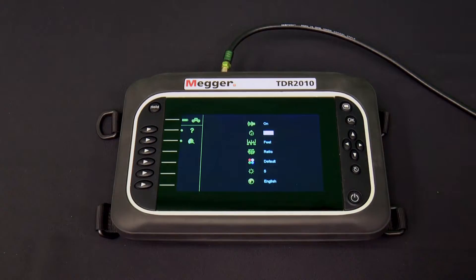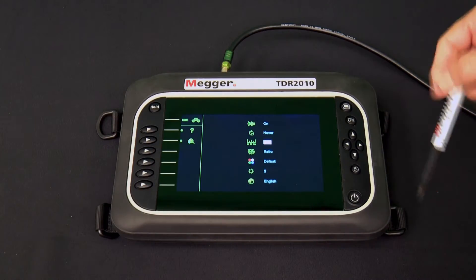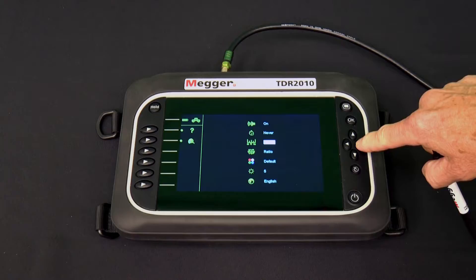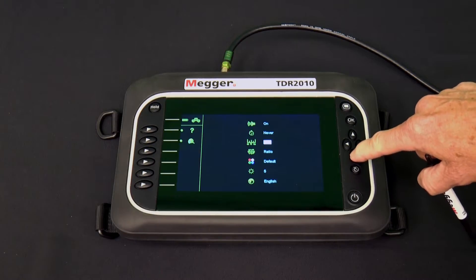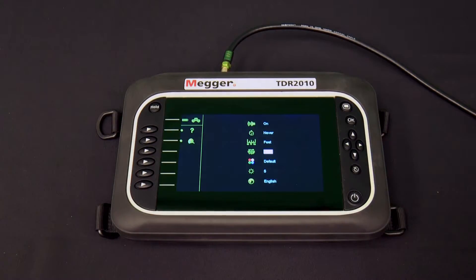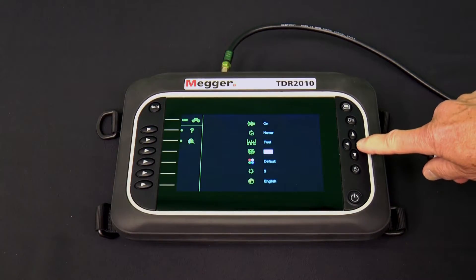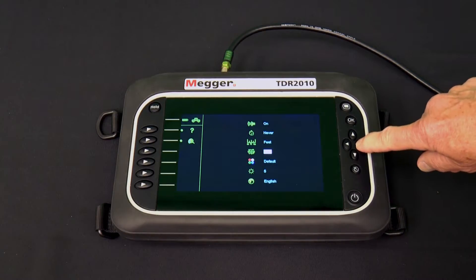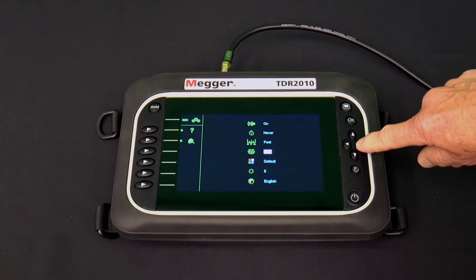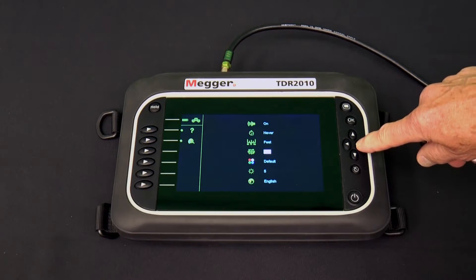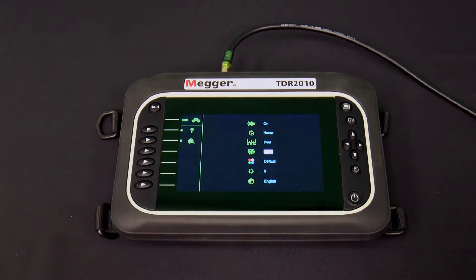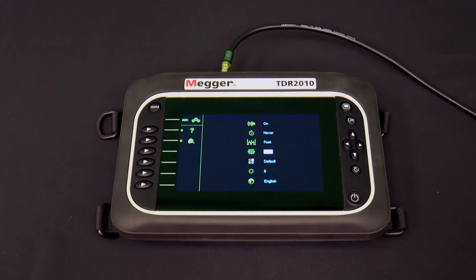The unit of distance measure, which is feet, meters, or nanoseconds. How the velocity of propagation is expressed — the choices are ratio, meters per microsecond, and feet per microsecond. We commonly use ratio, which is the ratio of the speed of light in our cable under test to the speed of light in a vacuum, which is a decimal less than 1.0.